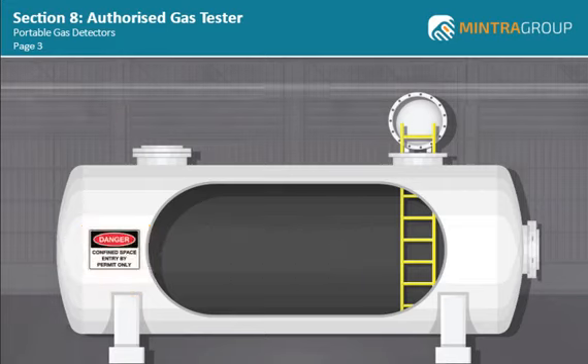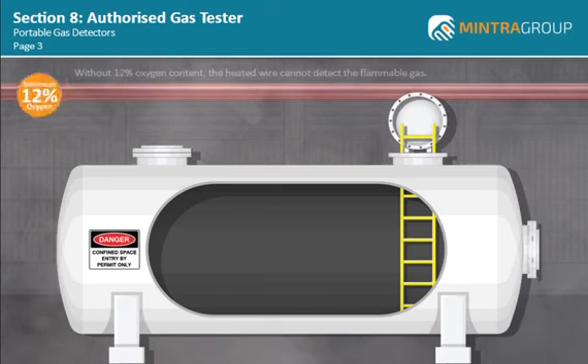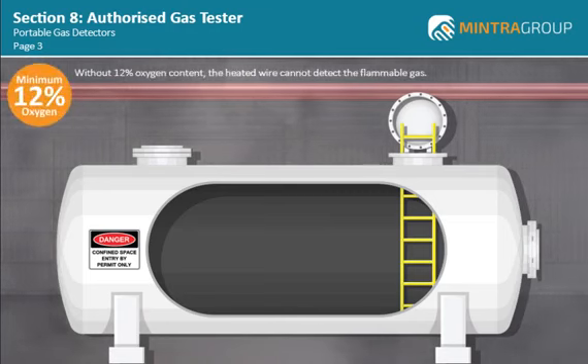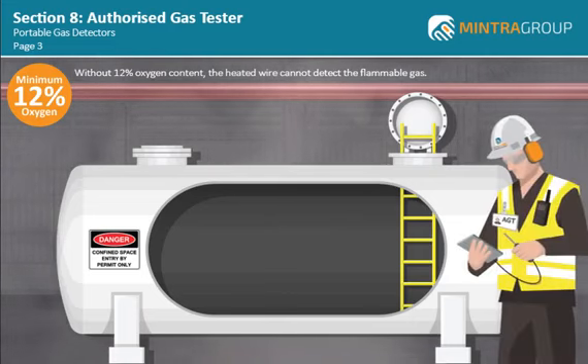Aspirated gas detectors require a percentage of oxygen in the atmosphere as the gas passes over a heated platinum wire to detect flammable gases. Under normal circumstances, these types of gas detectors are reliable, but without 12% oxygen content, the heated wire cannot detect the flammable gas. Therefore, as the AGT, you should be aware of the differences in the use of aspirated and non-aspirated gas detectors. If a representative gas sample is required in a nitrogen-purged confined space atmosphere, an infrared or similar non-aspirated gas detector should be used.